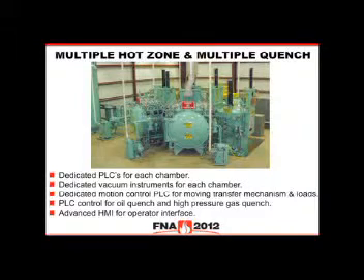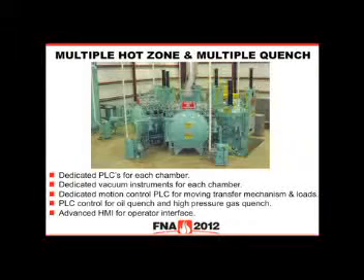The next level is a multiple hot zone vacuum furnace with multiple quenches. This particular unit has four hot zones, each with a dedicated PLC and dedicated vacuum instrument. Another PLC moves the load all around the system — from hot zone to oil quench to vestibule. There's typically another PLC for running the high-pressure gas quench and oil quench system, and then a sophisticated HMI for the operator interface.